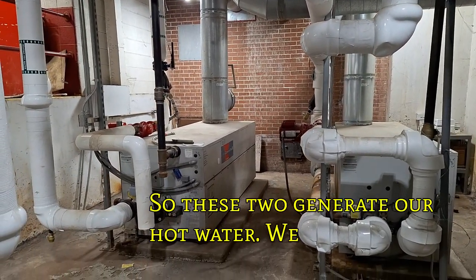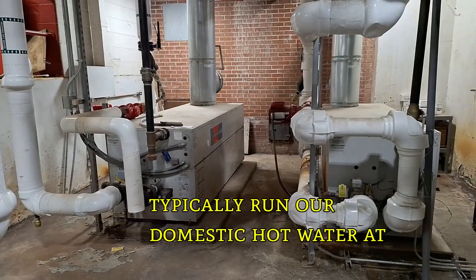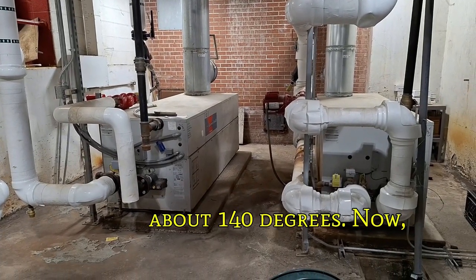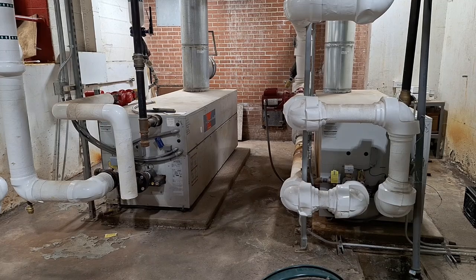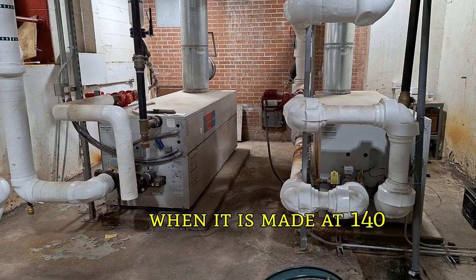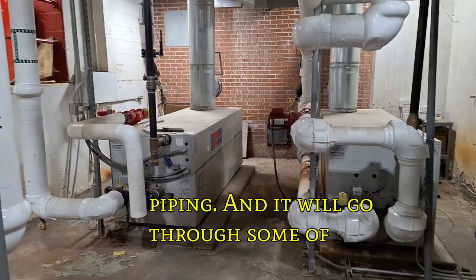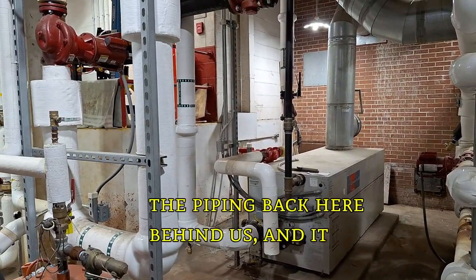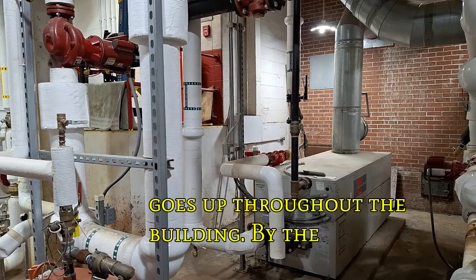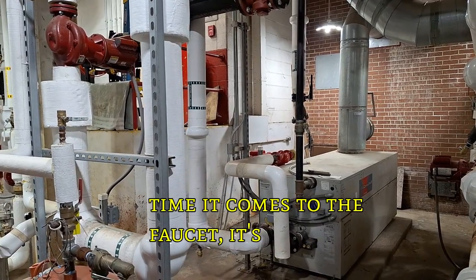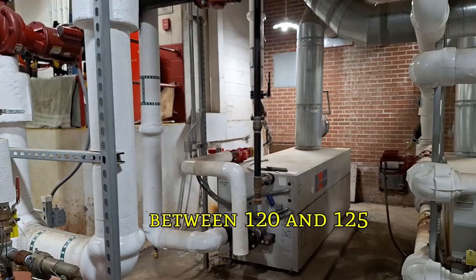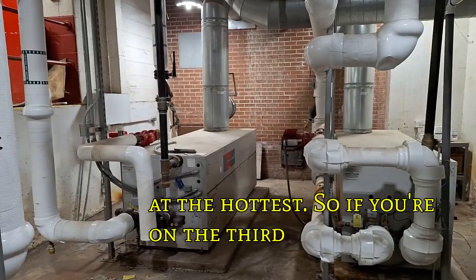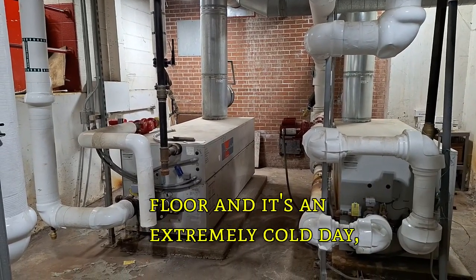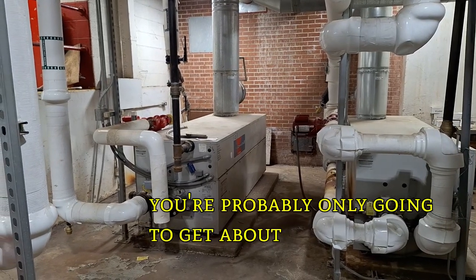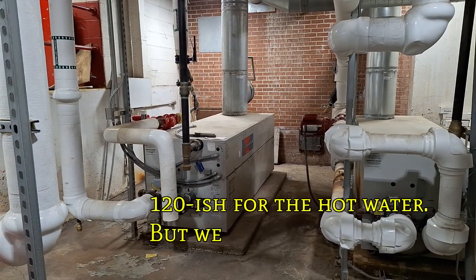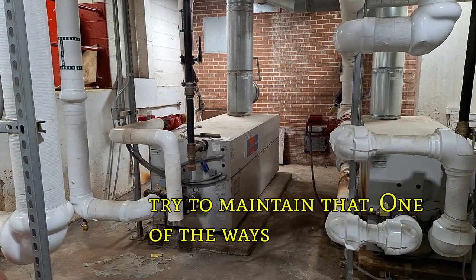So these two generate our hot water. We typically run our domestic hot water at about 140 degrees. When it's made at 140 degrees, it goes through all this piping, some of it back here behind us, and up throughout the building. By the time it reaches the faucet, it's between 120 and 125 at the hottest. So if you're on the third floor on an extremely cold day, you're probably only going to get about 120-ish for hot water, but we try to maintain that.